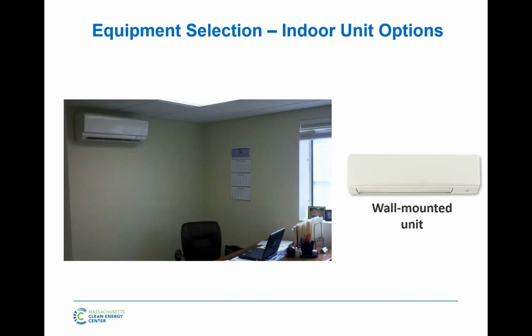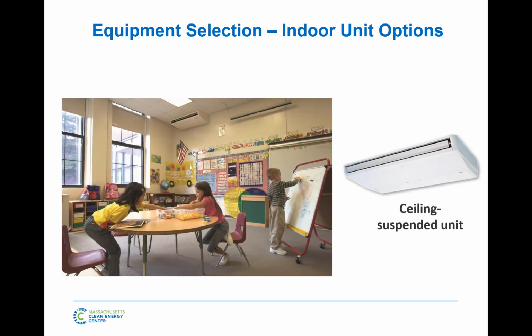Question over there. Yeah. So these units, the primary thing with a wall mount unit is to be as small and compact as possible. So there's just no place to connect ventilation air to. Once you have a unit like this that's a little bit bigger, all these other ductless units, most manufacturers give a knockout on the unit where you can introduce the ducted ventilation air directly to it. So on this unit, at the back of this unit, if we look at the direct opposite side of this on the back, there's actually a 4-inch round knockout that you can duct ventilation air into, and that will allow it to mix into the return airstream. About outside air? Yep, that's exactly what I'm talking about. Ventilation, fresh air, outside air, all the same stuff, yeah.